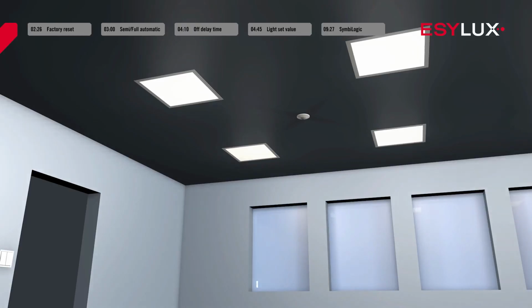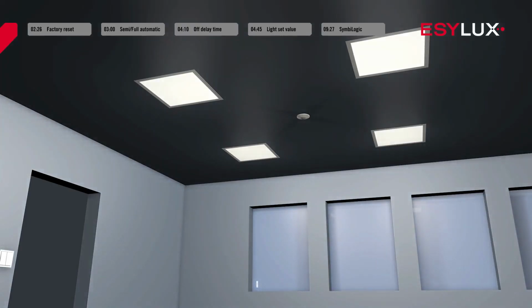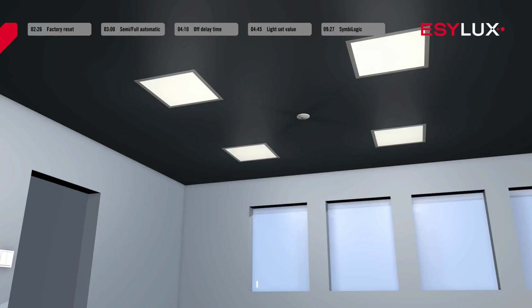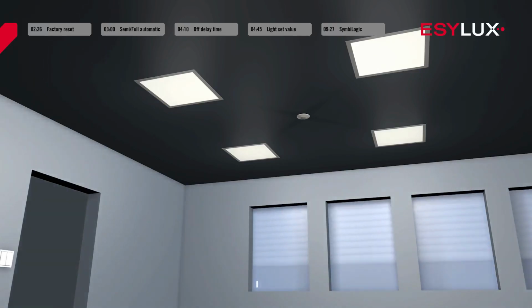If you use lights with additional light sensors, these sensors must be calibrated. Otherwise, the light sensor in the presence detector will be used, provided it is activated. A lux meter is required for calibration. If you do not have a lux meter to hand, you can also adjust the brightness manually. We will start with the more precise option, using a lux meter. If necessary, darken the room to prevent the calibration process from being disturbed by foreign light sources.